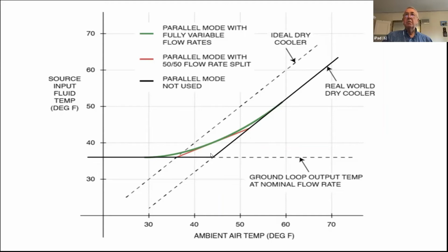If we're right here at an ambient temperature of, let's say, 44 degrees Fahrenheit, if we use the parallel mode, we're not stuck with 36 degrees Fahrenheit for the heat pump. We can go up to 40 degrees Fahrenheit. So we get a boost of temperature from using that parallel mode. That's why it's put in there. And the colors here just indicate right up here, the parallel mode with equal flow rates from both blocks. That's the red line. If we have totally variable flow rates, we can do a little bit better than that. That's the green curved line here.